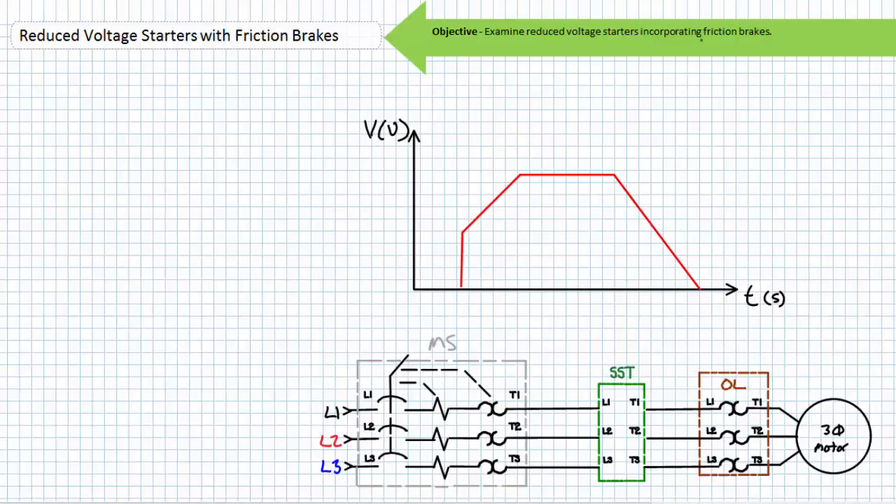Let's now examine a soft starter incorporating a spring-set electrically released friction brake. This scenario is a little bit more challenging than our previous scenarios and necessitates a re-examination of how we've been employing friction brakes thus far. A soft starter is a power electronics device that seamlessly ramps up applied voltage from a predetermined start voltage to full voltage over a predetermined ramp-up time. Advanced soft starter features also allow soft stops by ramping down voltage over a predetermined ramp-down time. Ask yourself the question: where does a friction brake receive full voltage when started and, for that matter, when stopped? As presently configured, it doesn't. During the ramp-up phase, the soft starter starts the motor at a predetermined start voltage and only after a predetermined ramp-up time is full voltage applied. A soft stop further complicates matters because applied voltage is progressively ramped down to zero volts over the predetermined ramp-down time.